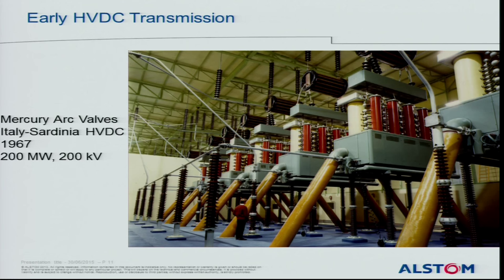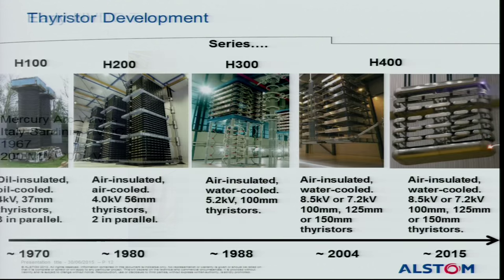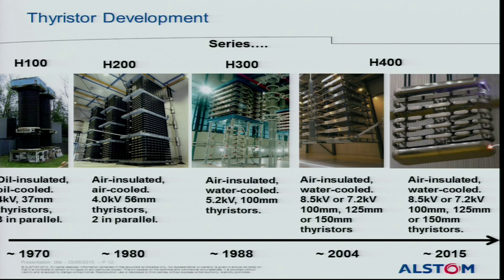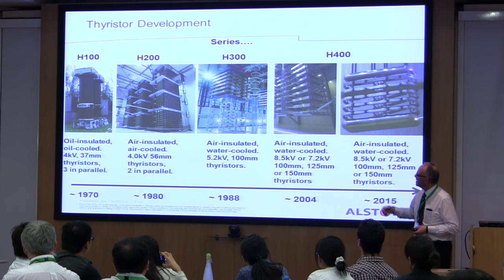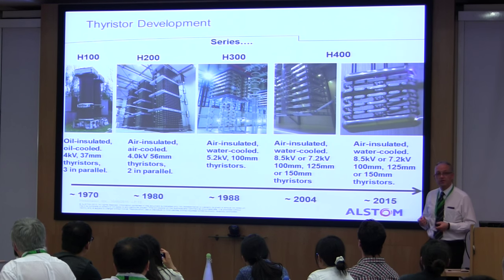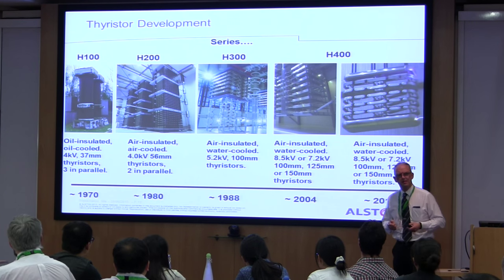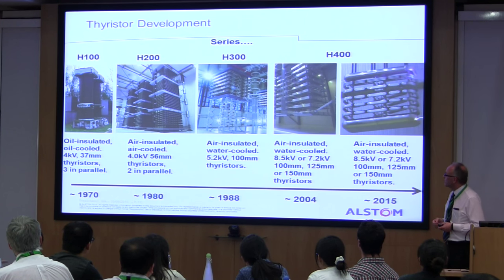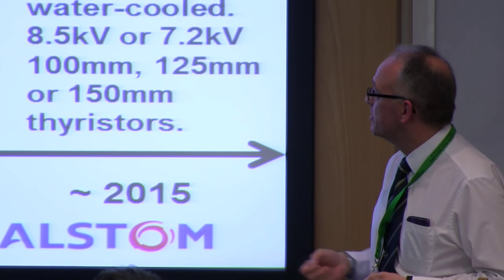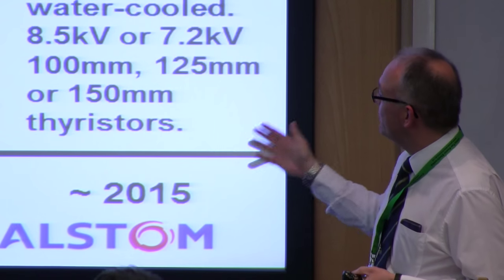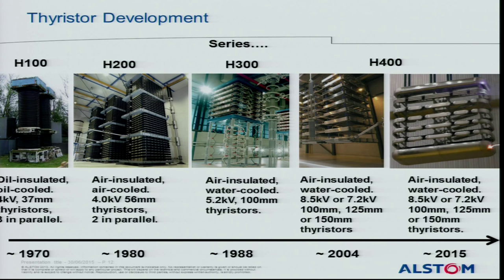Going back to history — early schemes in 1967 used mercury arc valves, which were being replaced by thyristors by the 70s. The technology has been driven fundamentally by the semiconductors. Early 70s we used 4 kV 37mm devices with three in parallel, outdoor porcelain cylinders, oil cooled. We went to air cooled in the 80s using 56mm devices, two in parallel — predominantly because the regulator at the time said you can't mix water and power electronics. Then in the 80s we did use water cooling: 5.2 kV, 76mm thyristors. Since the early 2000s, a more standard valve approach allows use of 8.5 kV or 7.2 kV devices at different diameters, optimised for the scheme.